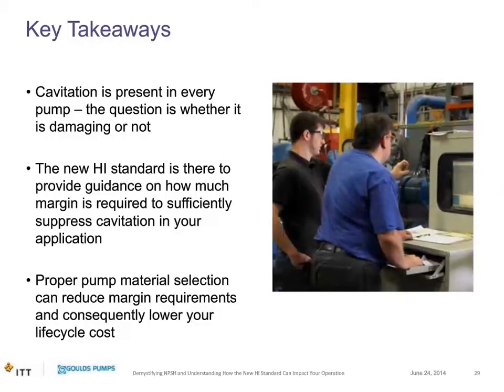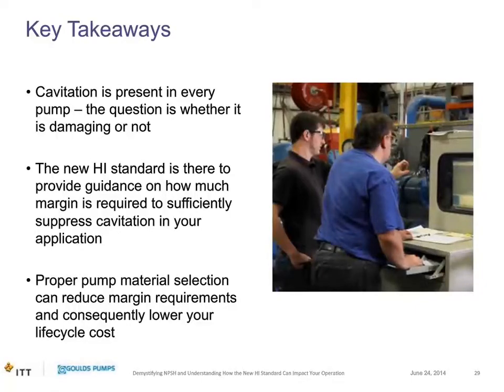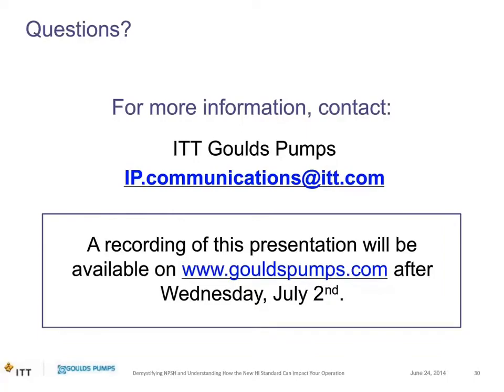Key takeaways: cavitation is present in basically every pump — the real question is whether it is damaging. The new HI Standard 9.6.1 provides guidance on how much margin is required to sufficiently suppress cavitation to achieve reliability in your application. Third, proper material selection can reduce your margin requirements and consequently may reduce lifecycle costs — so you need to weigh the cost of pump materials against total system costs. With that, we'll hand it back to Greg for questions.